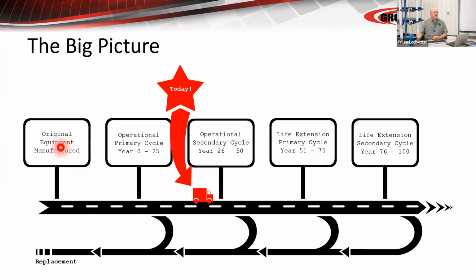So if you look at this timeline here, the original equipment was manufactured, let's say in the 80s, okay? The majority of the infrastructure in the US is late 70s, early 80s. Obviously, some of you have equipment that was put in in the 2000s, 2010, 2015, 2020, but the majority of the equipment was put in in the 80s. That's when the older air gear and the older oil gear was systematically replaced, primarily with vacuum. Now, today, there's still more air breakers in service than vacuum, but eventually all the air gear will be replaced. So in the first 25 years, your primary cycle was where the manufacturer thought it would be replaced.